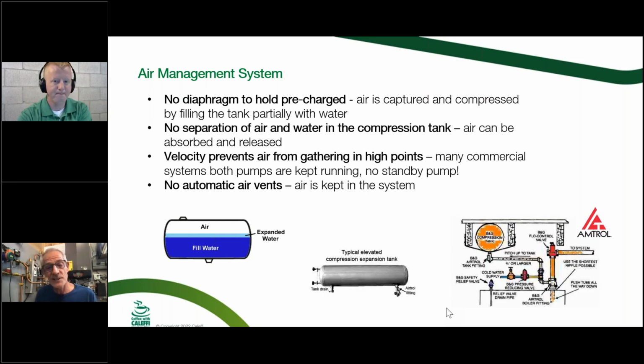And they'll typically have a sight glass on the end, in the middle picture there, so you can see where your air bubble is, and you know if your tank's getting waterlogged that it's time to get the air bubble back in there. Either pump some air into it, or drain it out, refill it again, and squeeze your bubble back in there. The tricky part is if anywhere in the system you have a little air leak around the valve packing or something like that, you can lose your airspace out of there. So yeah, you want to keep the air in.